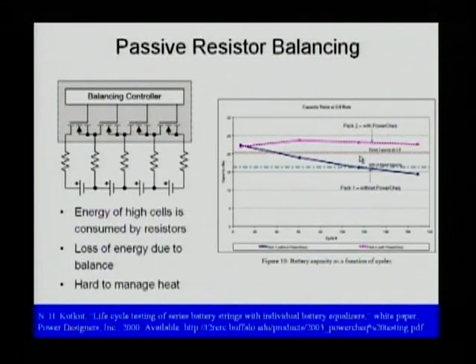A system like this provides a lot of benefits. A study done on lead-acid batteries about 20 years ago shows this in the chart: the pink curve is a battery system with balancing, the blue curve is without balancing. Over a 160-cycle test, the available capacity of the two systems ends up roughly 25% different.